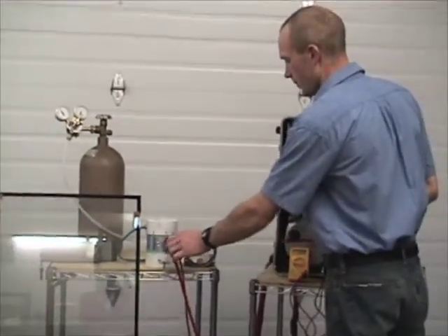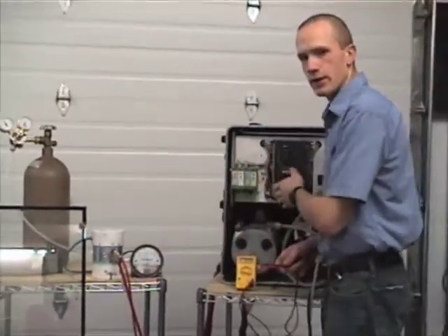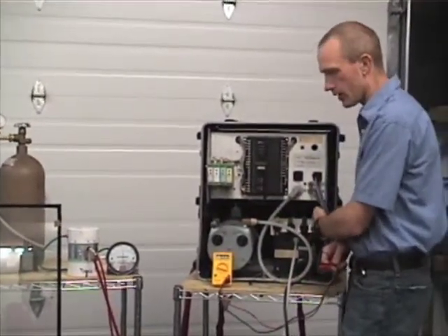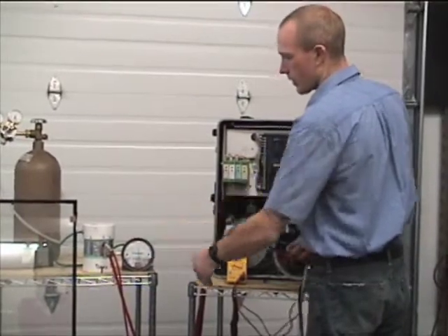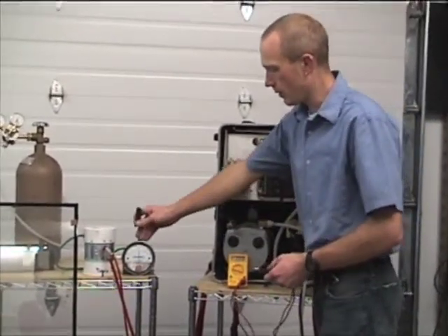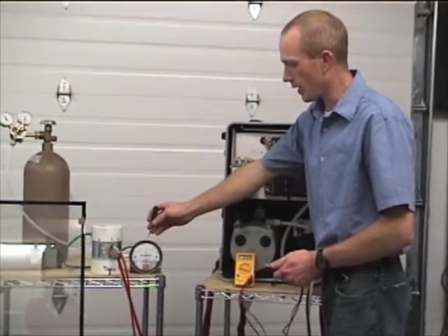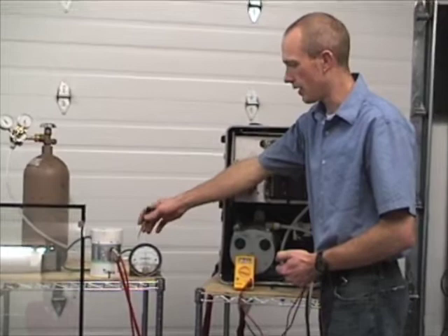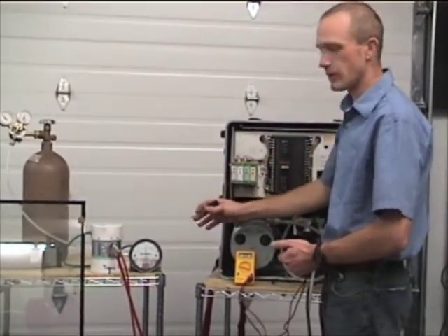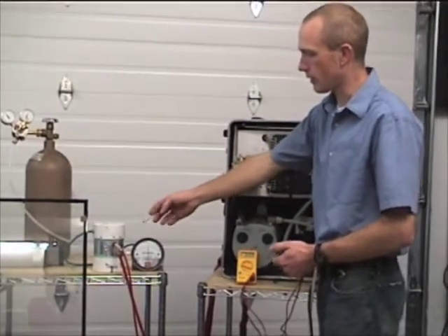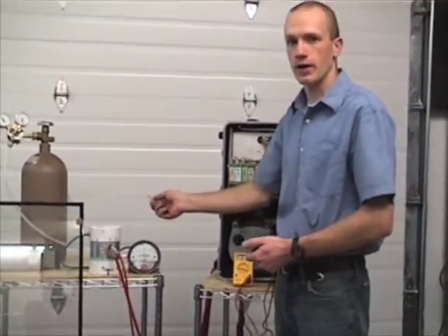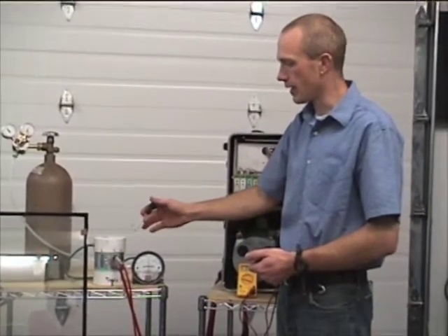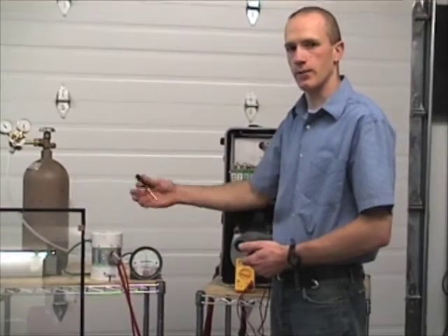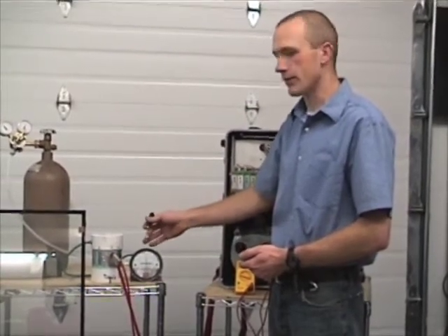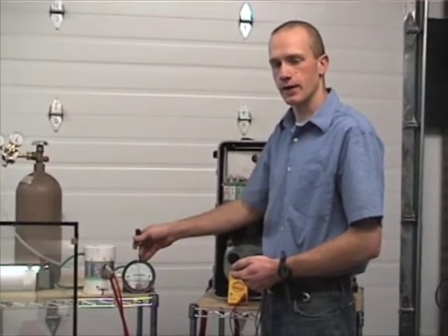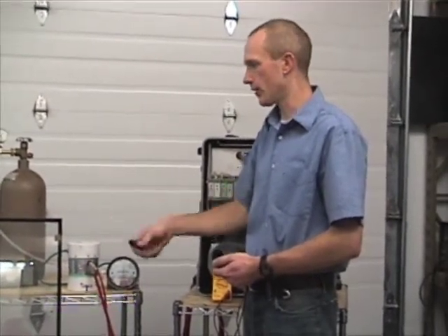So now that the lance is in there, we're going to start the machine and adjust a regulator inside the machine so that we can get a positive pressure on the magnehelic. Zero would be atmospheric pressure, and anything to the right would be positive pressure, and to the left would be negative pressure or vacuum. We don't want the machine to ever run in a vacuum state, because there's more vacuum than argon, and it's actually going to be sucking air from the room into that unit. It'll be constantly diluting it. So what we want is a little bit more argon than air, and that's going to keep the air from the room from entering that unit.